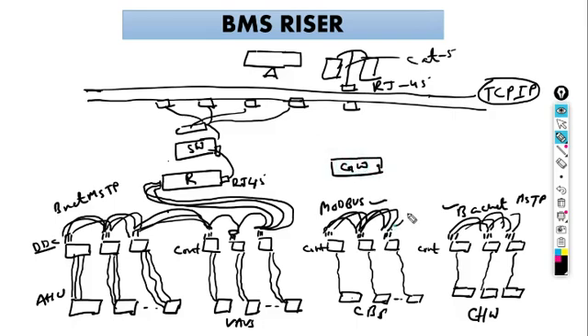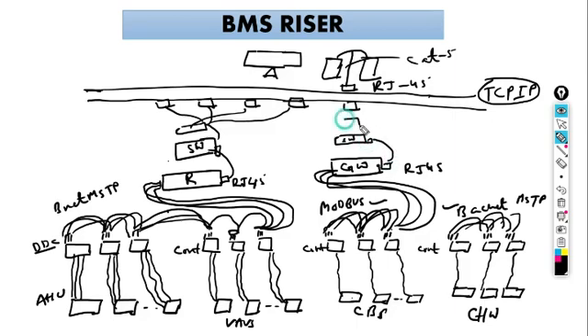So these are connected to the gateway, same as the 3-wire connection, on this port of the gateway, and it will convert to RJ45. It has two ports, one MS over TP and one RJ45. From that RJ45 we can go to the router, or we can go directly to a switch - another switch, or the same switch - through patch cables, through patch panels. These are PP patch panels, and through them this cable goes here. These are all fiber optic cable or Cat6 or Cat7 cable.